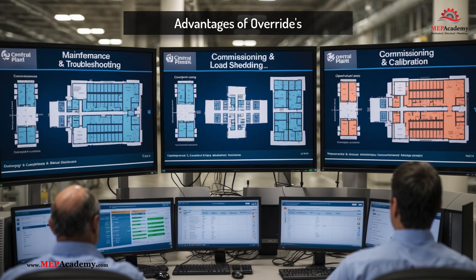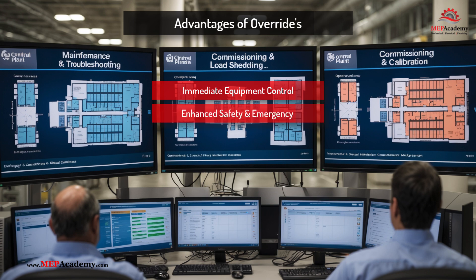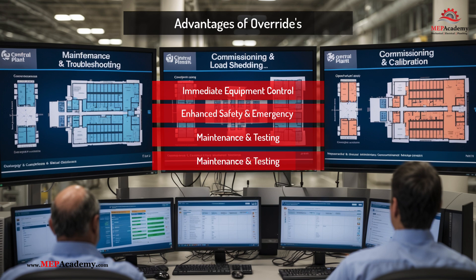Advantages of overrides: When used properly, overrides provide several benefits. Immediate equipment control allows technicians to manually operate systems when automation is malfunctioning. Enhanced safety and emergency response ensures life safety systems function when needed. Facilitates maintenance and testing by helping technicians isolate and troubleshoot faulty components. Provides flexibility for special conditions — adjustments can be made for specific events or unique situations. Energy cost reduction helps implement demand response strategies to reduce peak energy consumption.